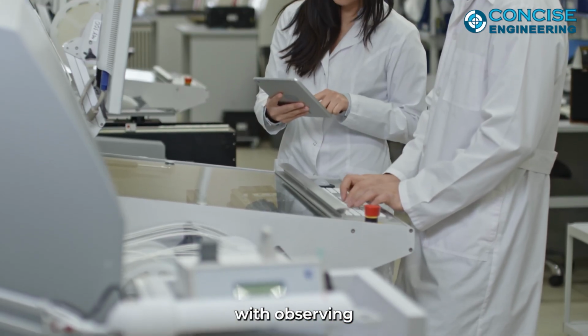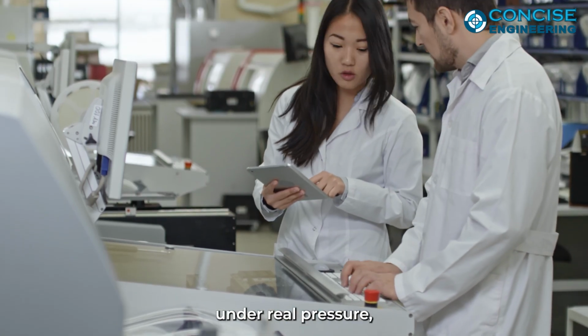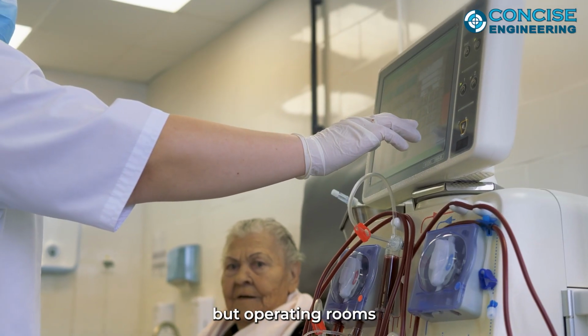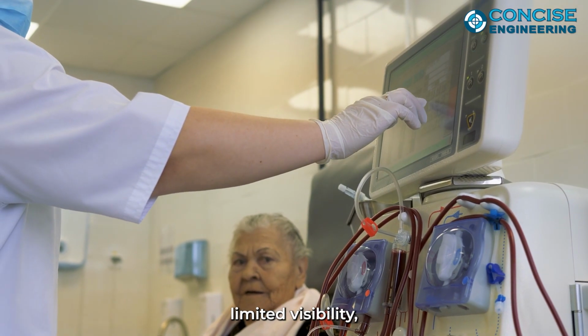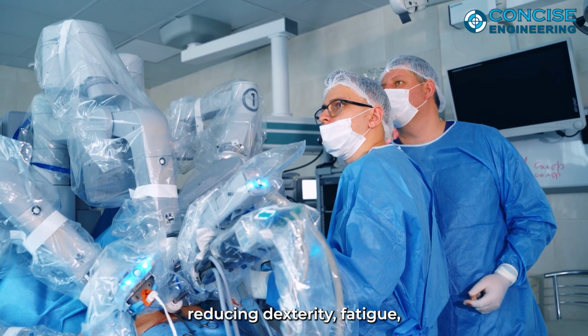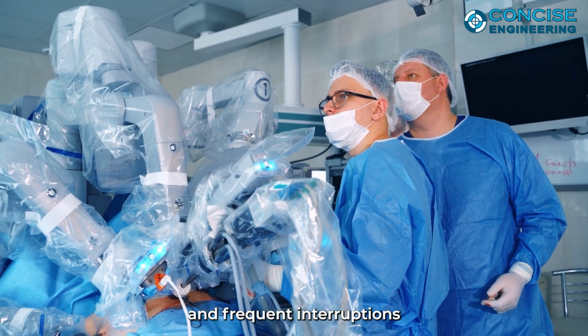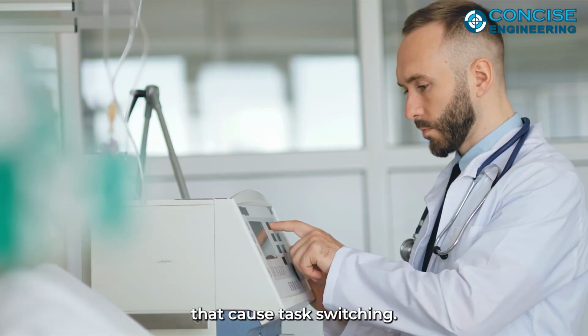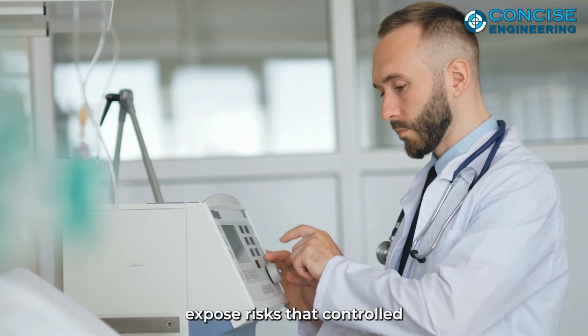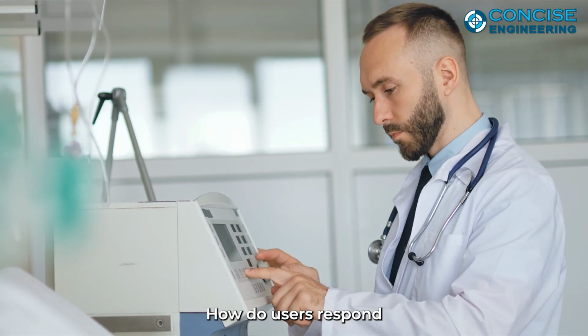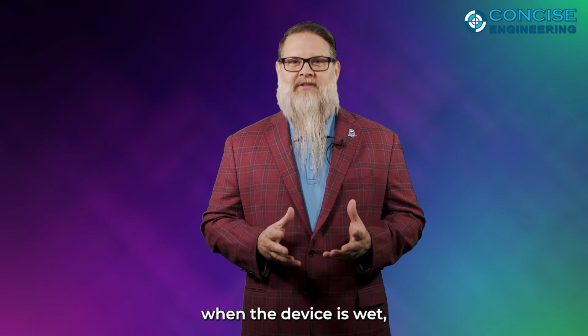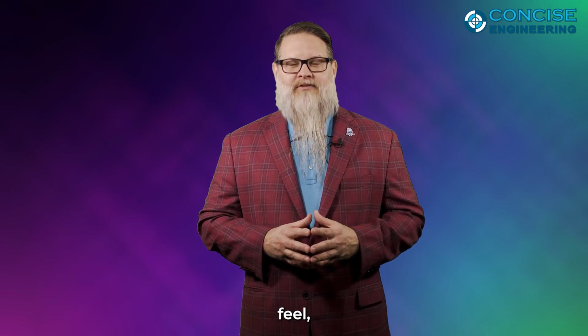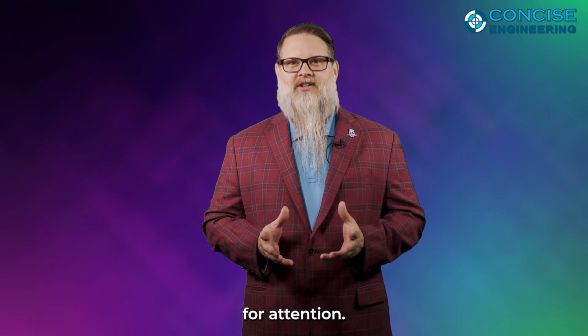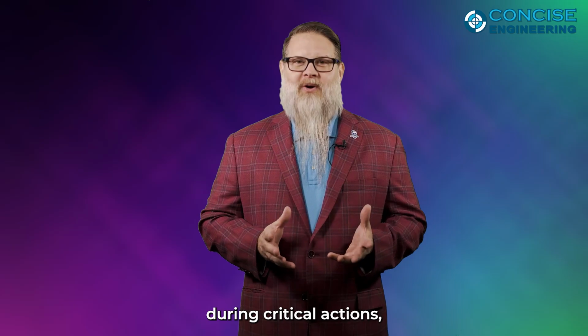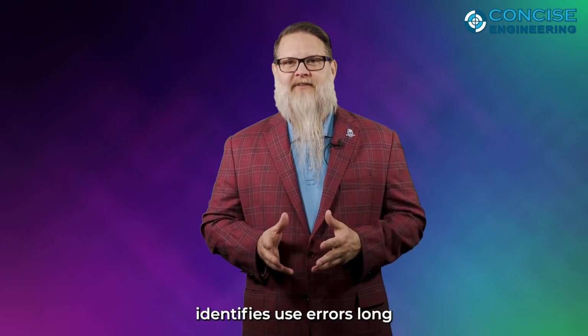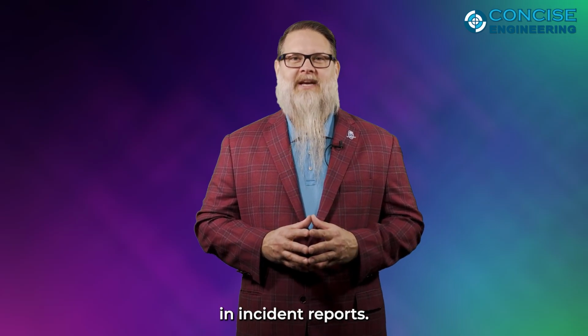Usability begins with observing real clinical workflows under real pressure, not calm lab environments, but operating rooms with alarms sounding, limited visibility, protective gloves reducing dexterity, fatigue setting in after long shifts, and frequent interruptions that cause task switching. These environments expose risks that controlled studies never reveal. How do users respond when the screen is partially obscured? When the device is wet? When gloves reduce tactile feel? When multiple steps compete for attention? When cognitive load spikes during critical actions? Clinical reality identifies use errors long before they show up in incident reports.